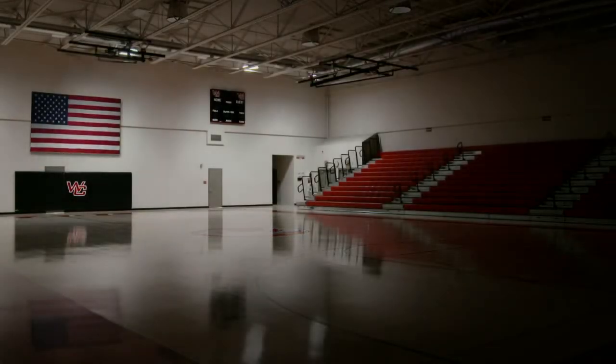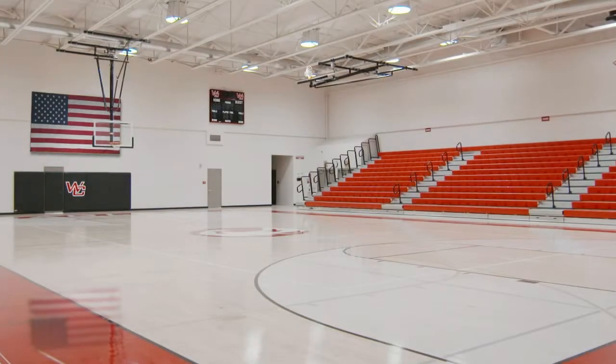It is a system that uses, in the commercial arena, low voltage controls. So we would connect to a 0 to 10 volt control system, the same system that you'd use to control an electric lighting system, but now we can fully modulate daylight levels from 100% daylight down to about 0.5% daylight. In a classroom setting, our typical classroom solutions are designed to modulate from 100% daylight down to about 1% daylight, which is sufficient to block out all the daylight so we're not interfering with projection, images, or screens in a classroom. But we still have sufficient daylight, even when it's fully dimmed, that the teacher can read facial expressions of the students.